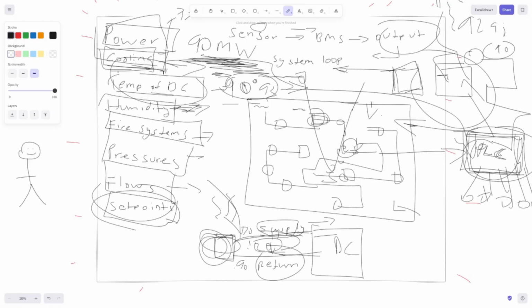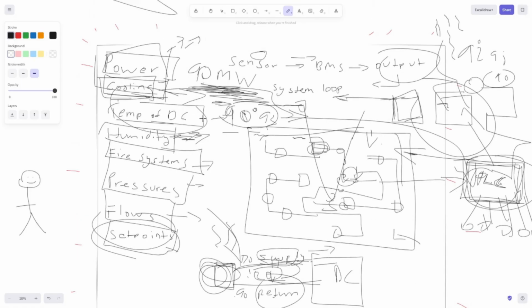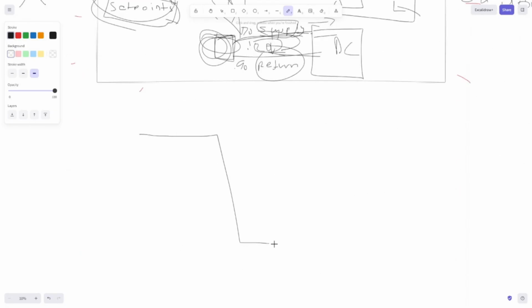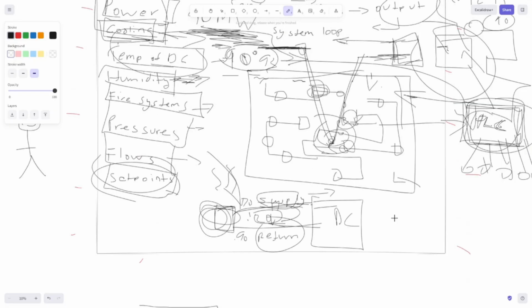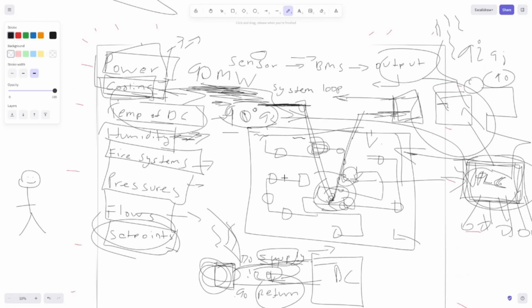I'm not looking at one number when I look at my whole BMS. I'm looking at the relationship of all of these numbers, right? Because the real value isn't the number itself, it's how the numbers move over time. Remember when I said if I'm looking at power, if I'm at like 90 megawatts and then I suddenly drop to 50 and then I go back up to 90, I'll ask myself, what happened here, right? And I'll find out what happened here. Because this could easily turn into 90, 90, 90, drop, and then we're at 0 or 50, which is horrible. We don't want that, right?